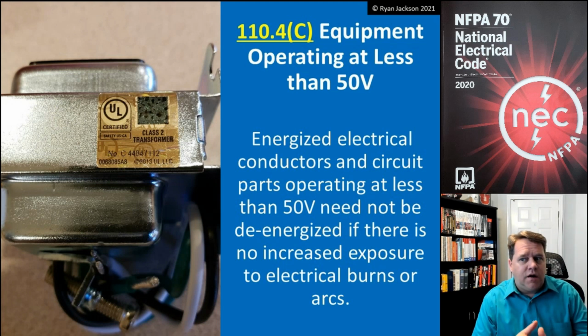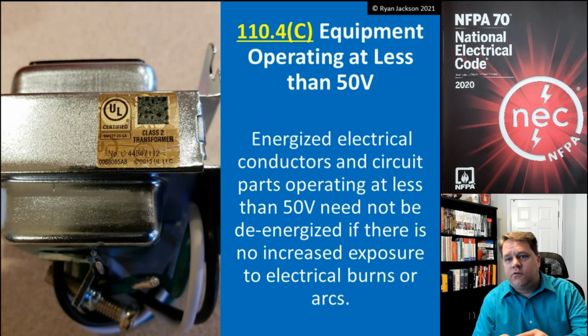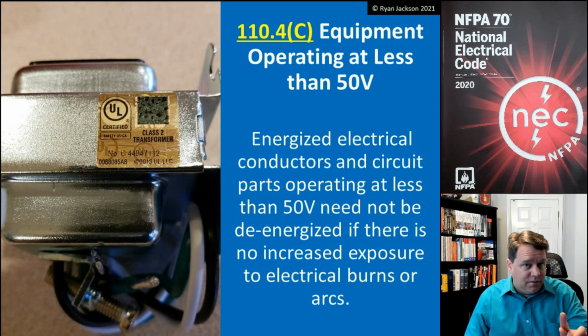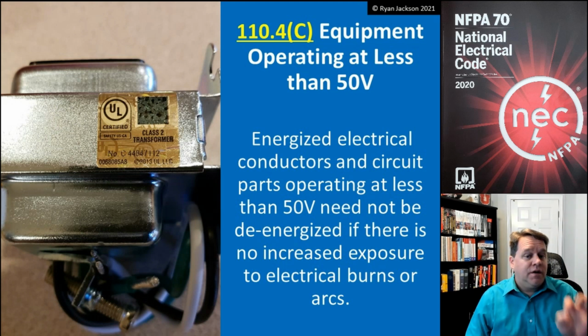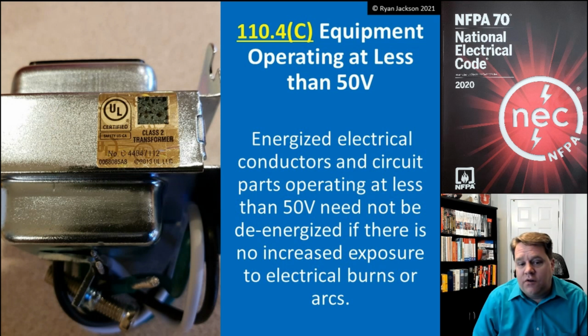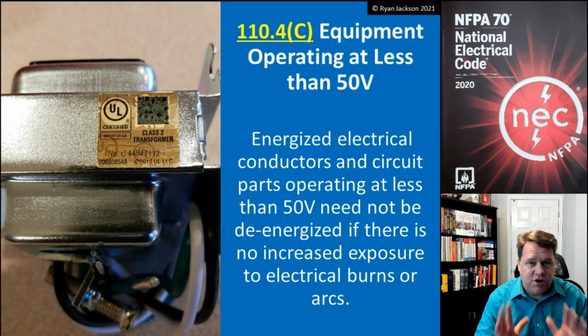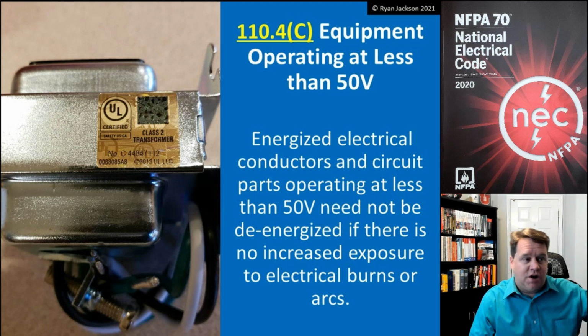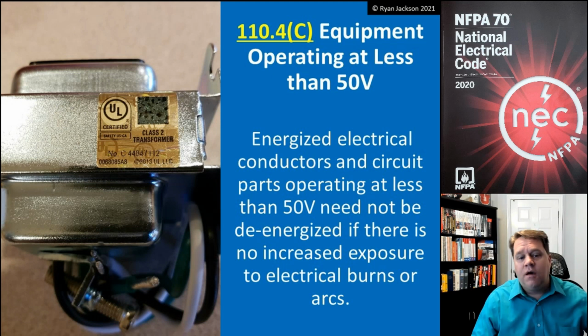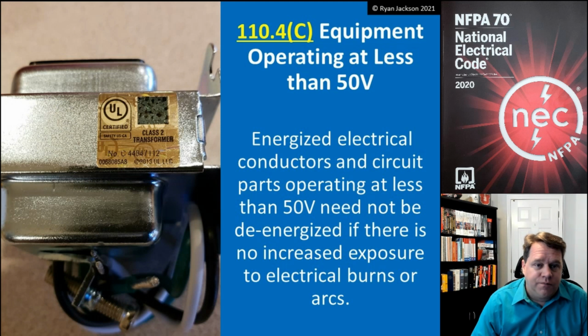So yes, I can work energized on 50 volts and less if, and that's where we need to keep reading, if there's no increased exposure to electrical burns or arcs. So it's not just a carte blanche exception, 50 volts and you can work energized. That's really not the case. It's only if there's no increased exposure to burns or arcs.